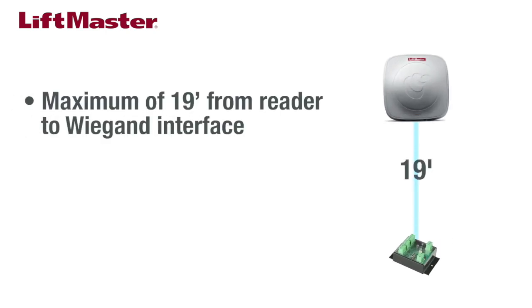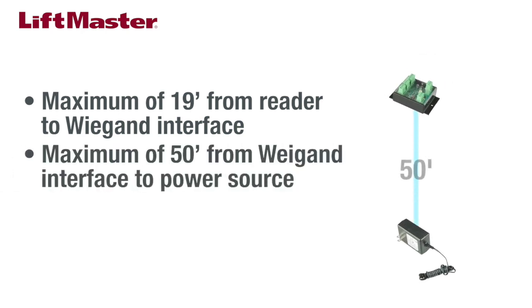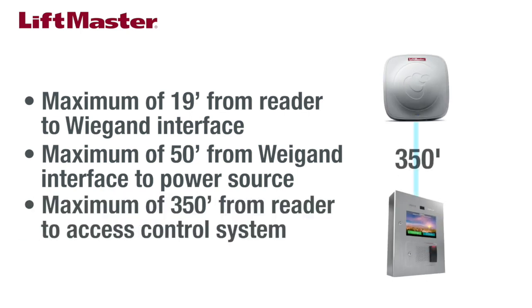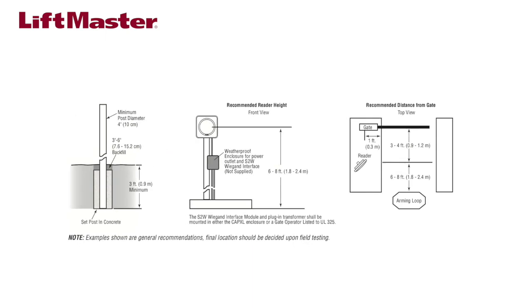The maximum length of wire between the reader and the Wiegand interface inside the enclosing CAP XL or gate operator is 19 feet or less. The maximum distance between the Wiegand interface and the power outlet inside the gate operator should not exceed 50 feet using 18-gauge stranded wire. The maximum distance between the reader and the access control system should not exceed 350 feet using 18-gauge stranded wire. Refer to the manual for additional guidance on optimal placement of the reader.